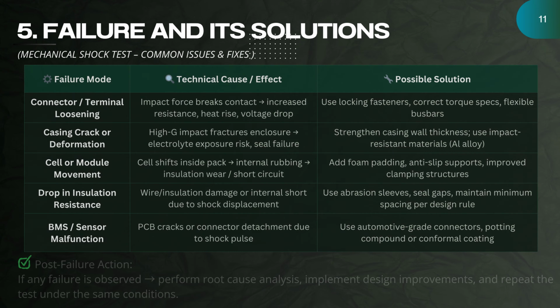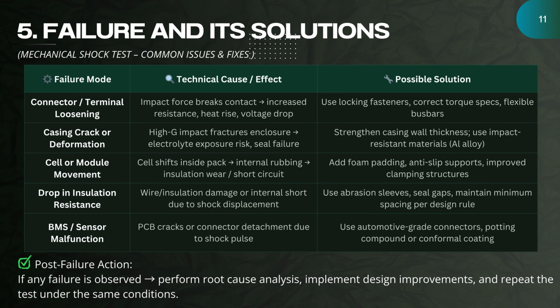Let's look at what typically fails and how to fix it. Connector and terminal loosening is very common. The fix is locking fasteners, correct torque, and flexible bus bars. Casing cracks happen when the enclosure can't handle the G-force, use thicker walls or impact-resistant aluminum alloy. Cell movement inside the pack can cause internal shorts. Foam padding and better clamping structures help.